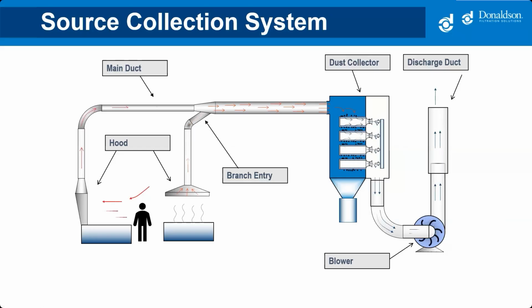that's representing the pulse cleaning system that dust collectors have, and this is a very important subsystem that back pulses the filter. So it's actually shooting a small blast of air backwards through the filter, and that creates a ripple effect through the filter that knocks the dust cake off the filters. And so this is really important because it gives you long filter life. So filters load up with the dust cake, the pulse system knocks that dust cake off, and then the filters can load another one, and then the process just continues to repeat until the filters ultimately cannot be pulse cleaned anymore and you have to replace them.